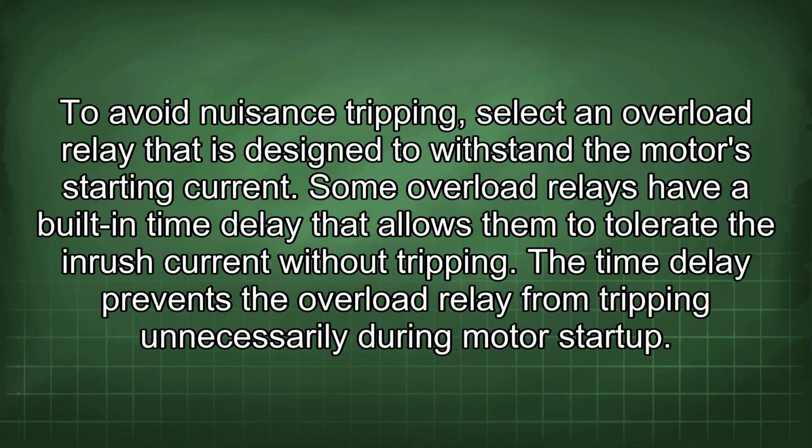To avoid nuisance tripping, select an overload relay that is designed to withstand the motor's starting current. Some overload relays have a built-in time delay that allows them to tolerate the inrush current without tripping. Time delay prevents the overload relay from tripping unnecessarily during motor startup.